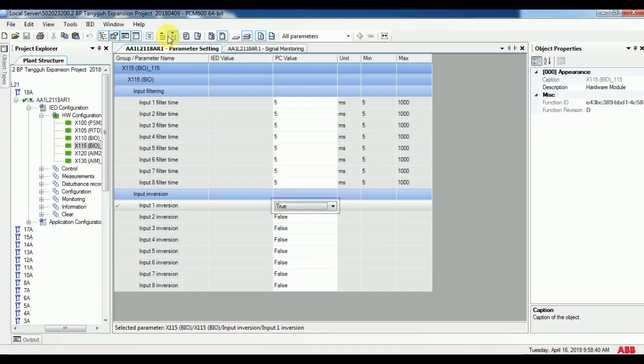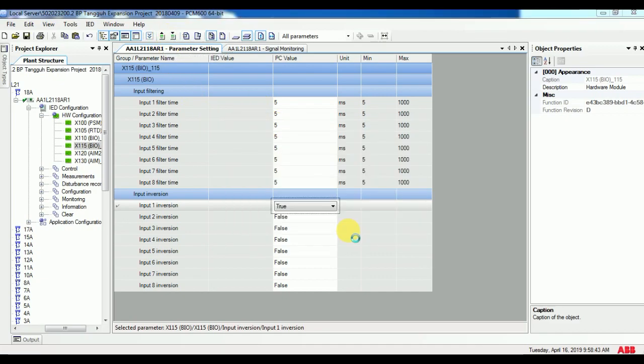On X115 card, I am going to trigger input 1. So click on X115 under HW configuration. In the parameters, you can see the option input inversion. Make it true and write to the relay.